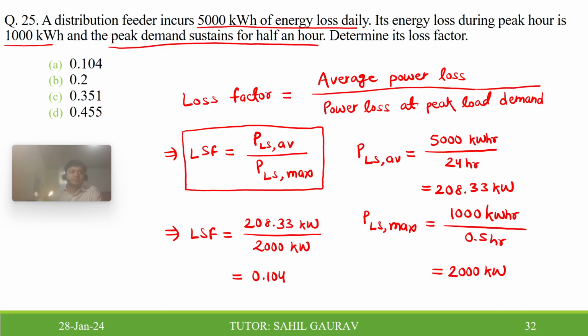So how can you determine the average power loss? The energy loss is given, so 5000 kilowatt hour divided by the number of hours, 24 hour, will give you 208.33 kilowatt. And then we have to find the power loss at peak load demand. So it is 1000 kilowatt hour, and the number of hours is 0.5 hour, so it will give you 2000 kilowatt. Just put both the values in the loss factor expression, you will get 0.104. So A is the correct option.